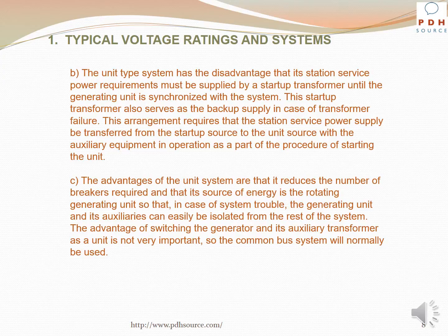The advantages of the unit system are that it reduces the number of breakers required and that its source of energy is the rotating generating unit, so that in case of system trouble, the generating unit and its auxiliaries can easily be isolated from the rest of the system. The advantage of switching the generator and its auxiliary transformer as a unit is not very important, so the common bus system will normally be used.